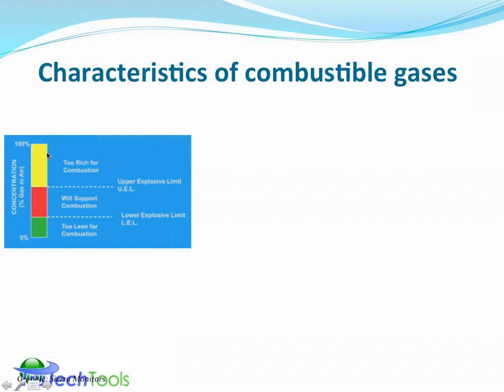Because as soon as it moves from this too rich range above the upper explosive limit, and the gas concentration drops back down, it can drop back through into the combustible range just by dispersing or having the source of supply set off, or the gas cloud moving through an area. So it can drop from the upper explosive limit into the explosive range before it gets to below the lower explosive limit. So that's why we want to pay attention to these two levels, upper and lower explosive limit. And usually, in most situations, we want to constrain ourselves to being below the lower explosive limit.